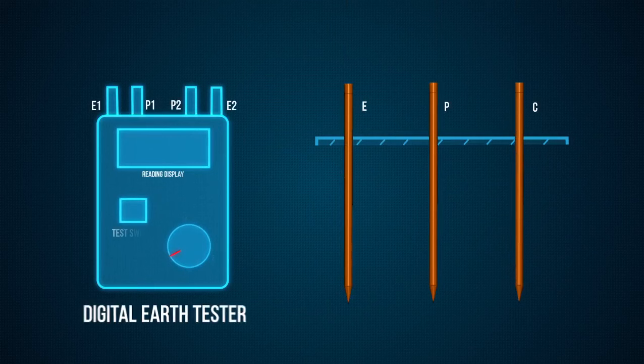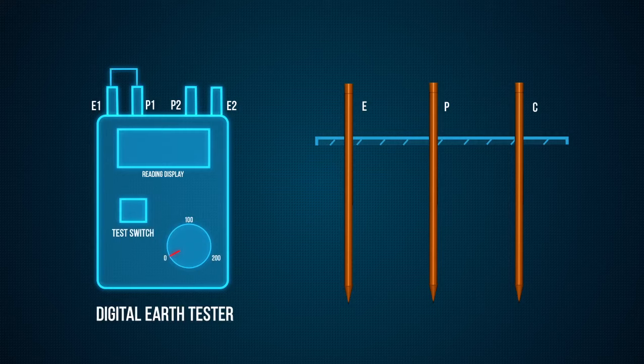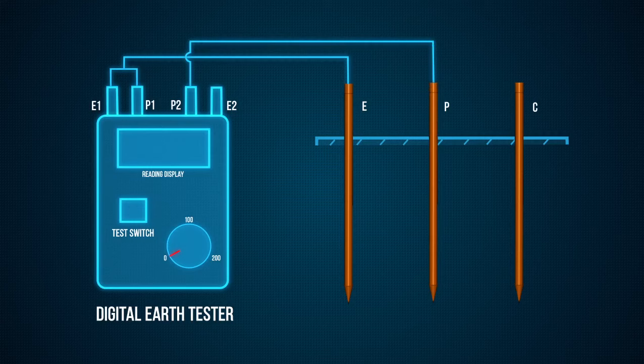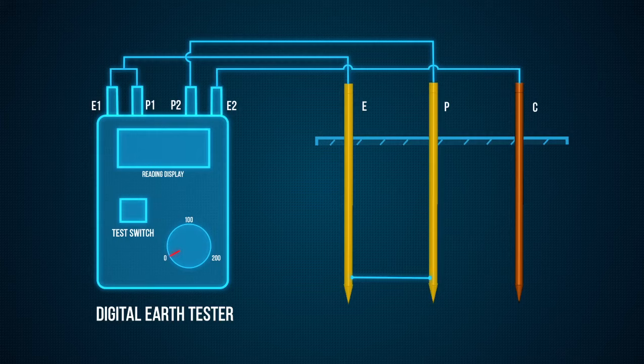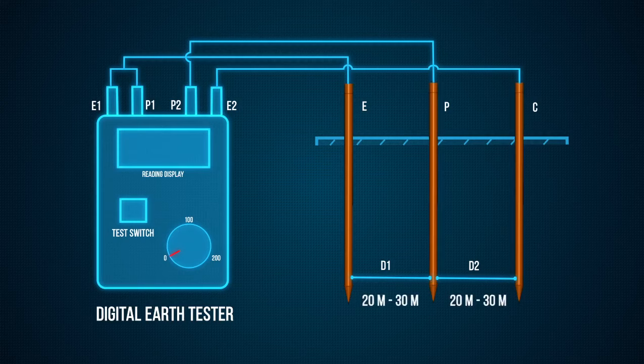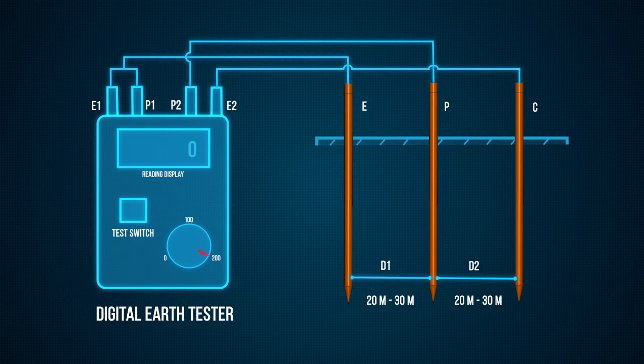Measurement of earth electrode resistance. The digital earth tester has four terminals. Short the terminals E1 and P1 and connect to the earth electrode E whose resistance has to be found. Connect P2 to the potential spike P and E2 to the current spike C. The distance between earth electrode and potential electrode is D1, and D2 is the distance between potential electrode and current electrode. These distances may range from 20 to 30 meters depending upon the soil. Turn the range selector switch to select a proper range for ohm. The digital display will come in action and will read zero. Now press the test switch. The LCD display will indicate the resistance.